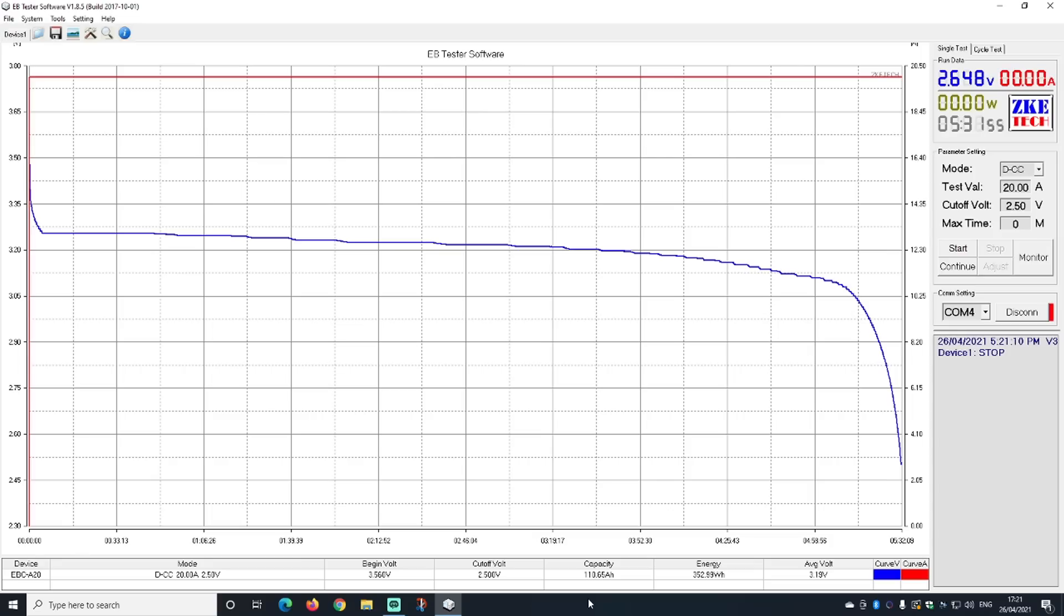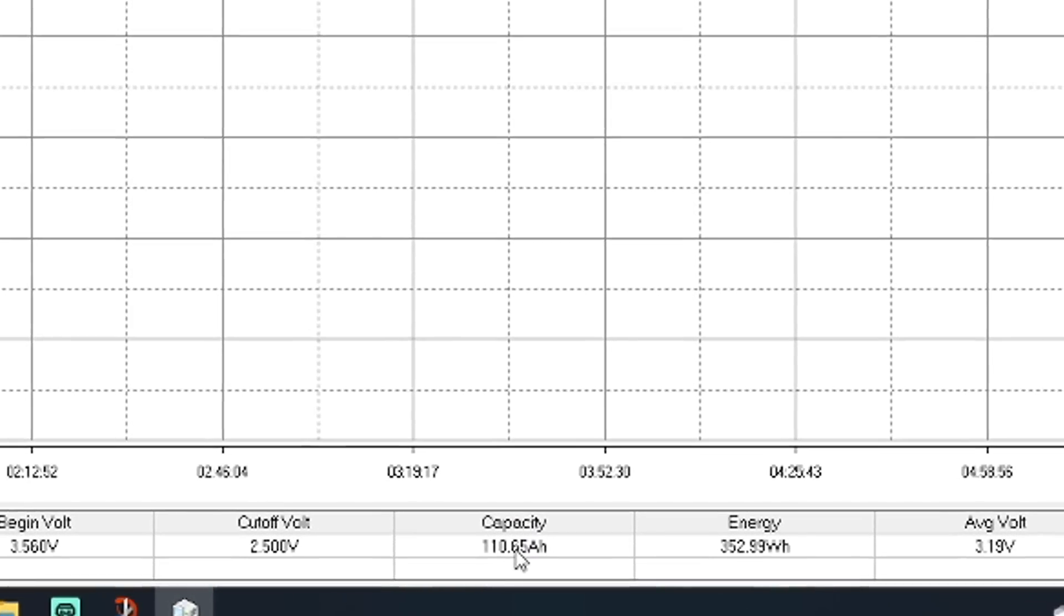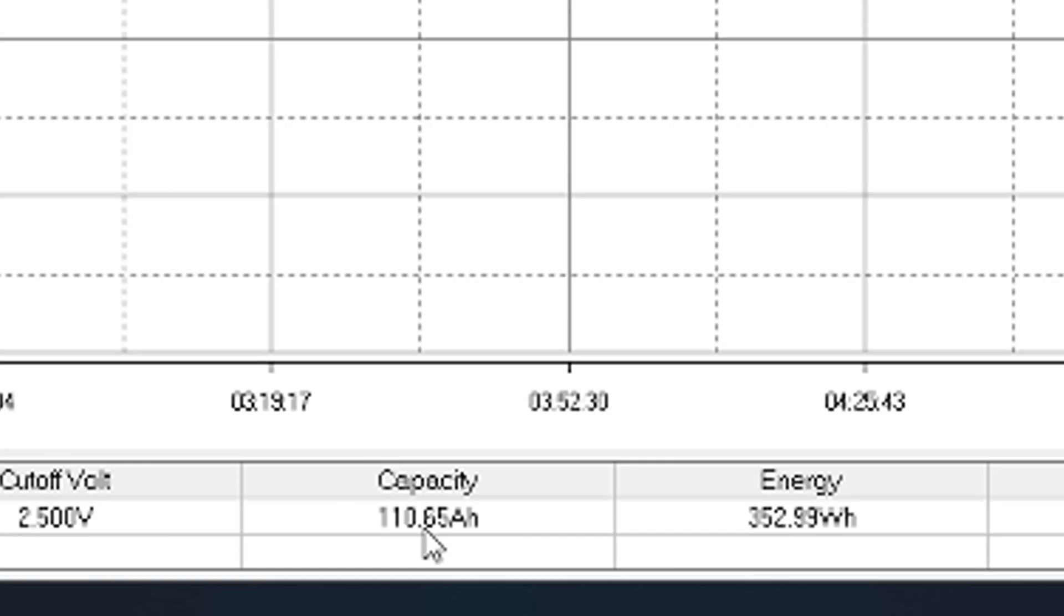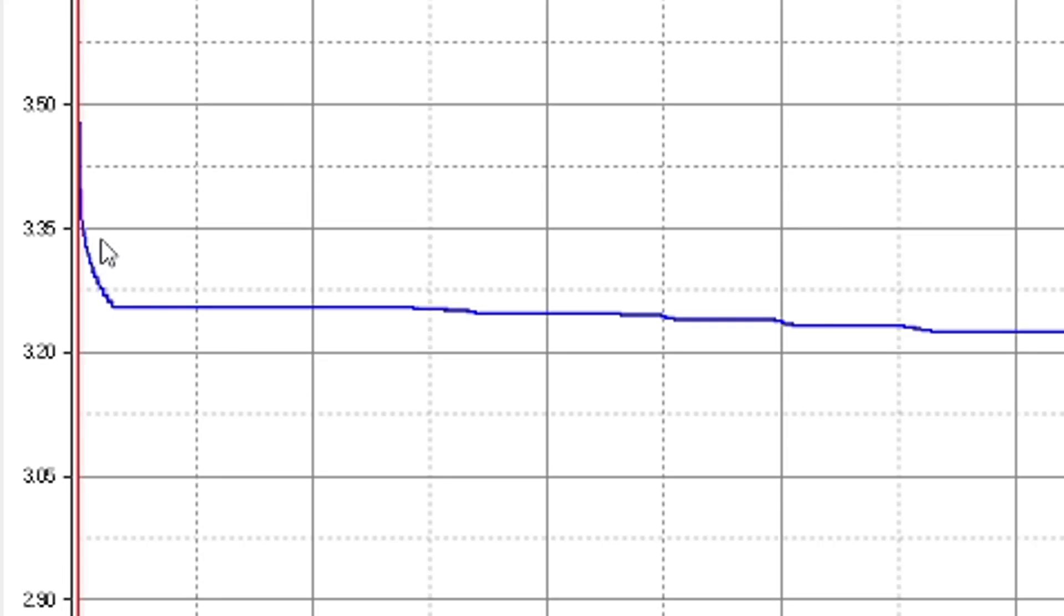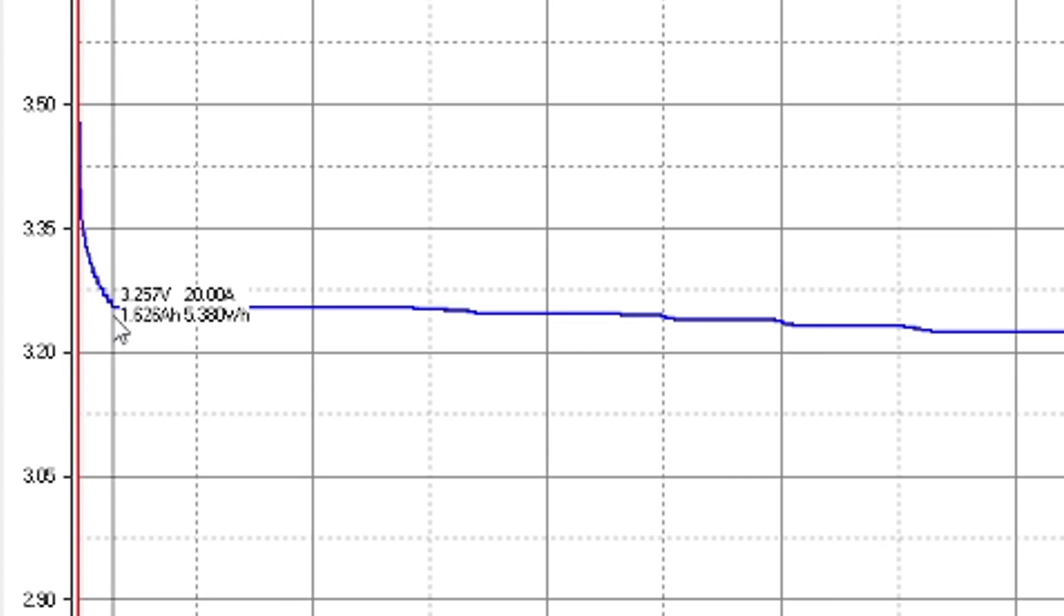So, well, here's our discharge curve of this cell. Firstly, I'm super impressed with this battery cell. Look at this result down here. We were able to discharge the battery with 110 ampere hours for a rated 100 ampere hours. So, 10% more capacity. That is a lot. That is super nice. We can actually press the right mouse button on the curve and it gives you information about how much ampere hours we have discharged at exactly this point. This is 3.257 volts. This is where the flat area of the curve started. And at this point of time, we have discharged the battery with 1.6 ampere hours only.